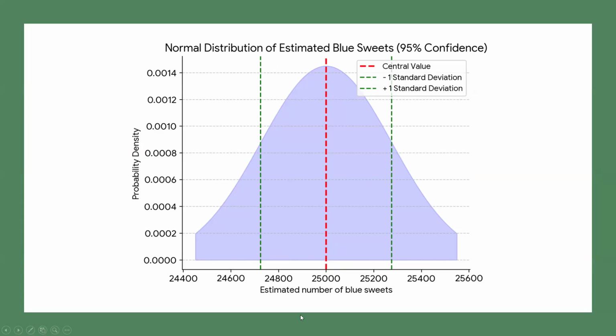So this is the 95% confidence interval. All of your observations, or 95% of your observations if you repeat it an infinite number of times, would sit between this value here and this value here. And this is the 95% confidence interval with a central value, which you're assuming is the real value. In some reports and information, 1.96 or 2 is often described as a coverage factor, which is effectively what you multiply the standard deviation by to give you a range of values that your estimate falls within.